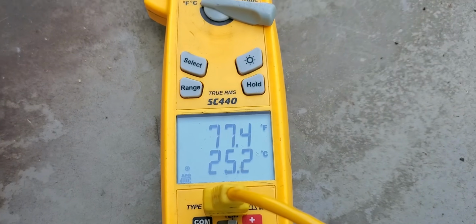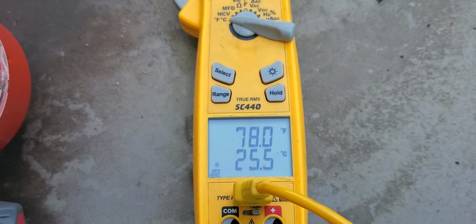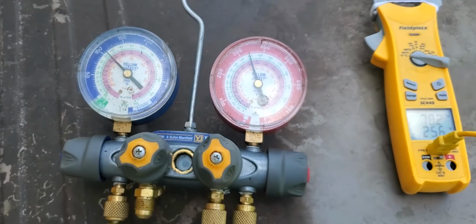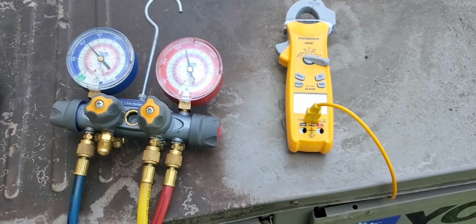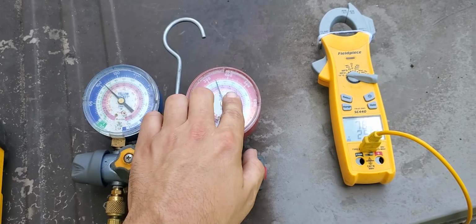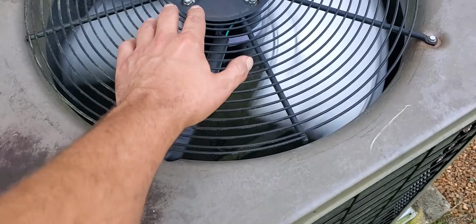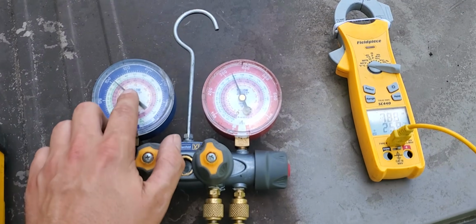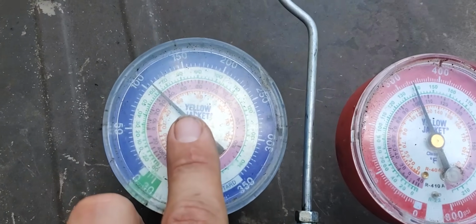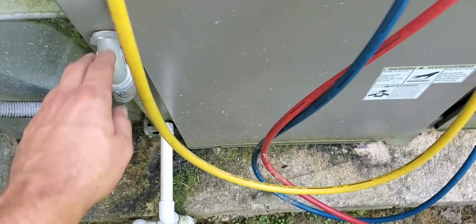Now, measure the temperature of the suction line near the compressor. When using a thermometer with a sensing probe, secure the probe to a flat, clean area of that suction line and wrap it in insulation. This practice will prevent ambient air from affecting the temperature reading. Superheat and subcooling calculators are useful for this step. Record that suction line temperature.